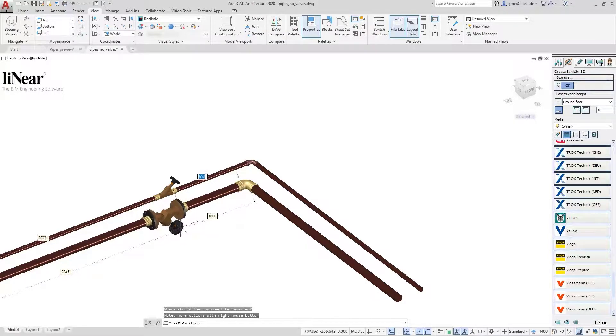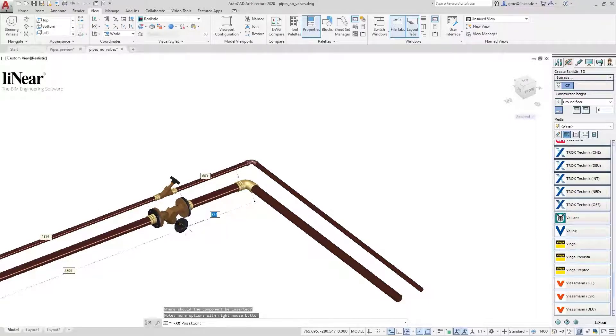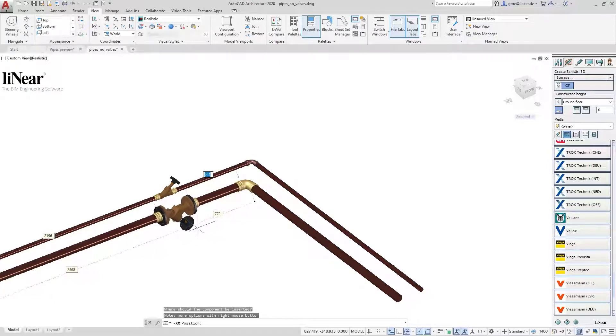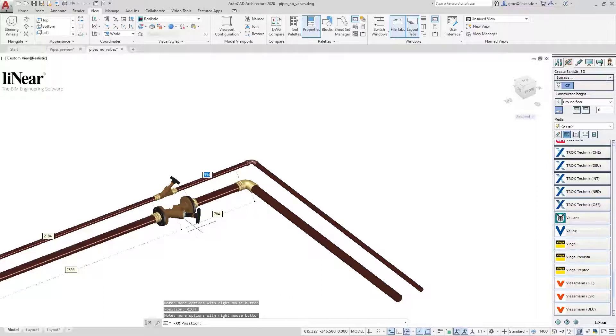The upper dimension reference gives me the distance to the elbow — exactly to the end of the pipe including the insertion depth. I therefore use it to determine how long the pipe should be between the flange and the elbow. The second dimensional reference measures the distance to the pipe behind the elbow. Based on this information I can position the components with millimeter precision.